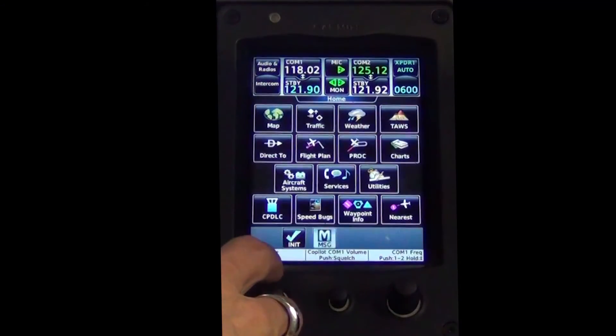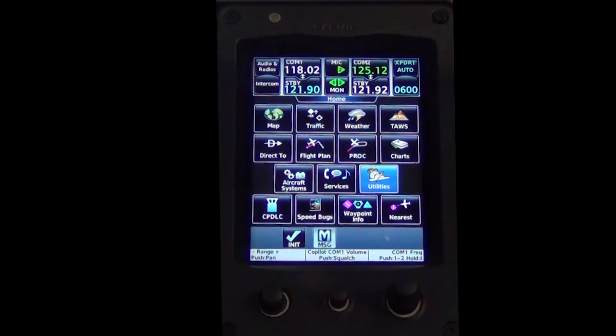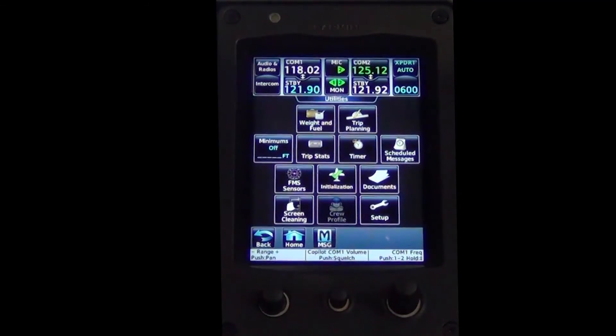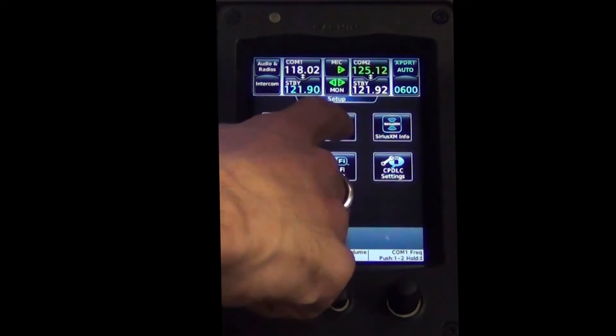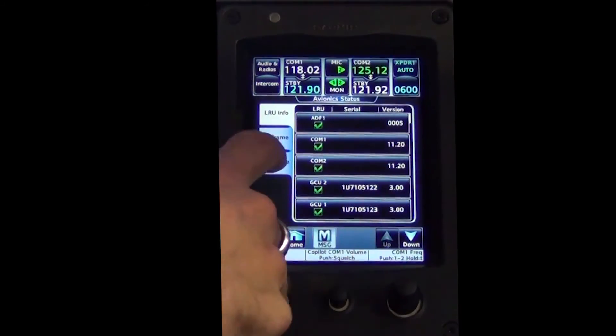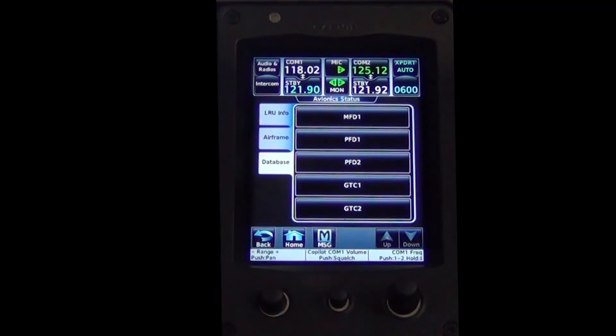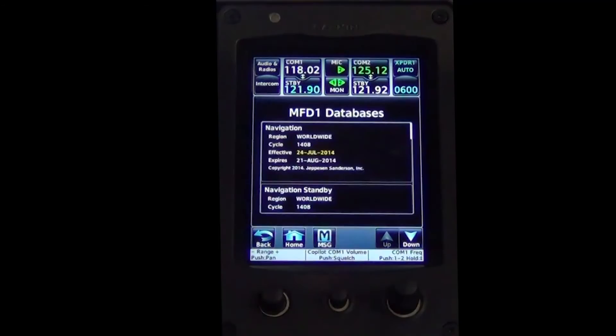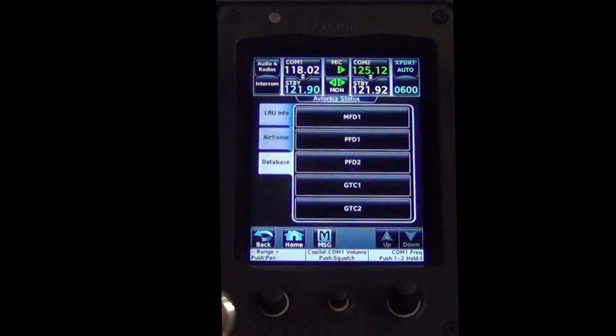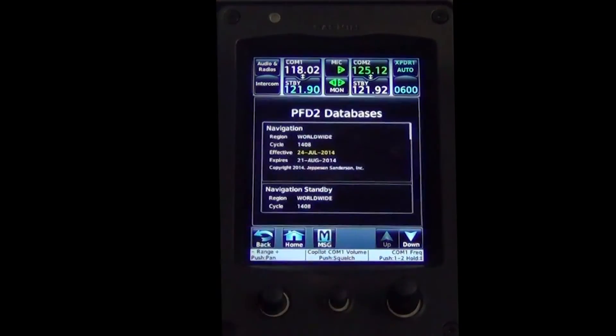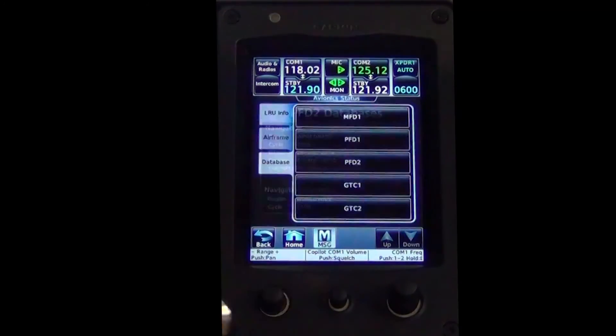From the home screen on the GTC, select Utilities, then Setup, then Avionic Status, and then Database. You will now verify the expiration date on the MFD, PFD1, PFD2, GTC1, and GTC2 to ensure the update was successful.